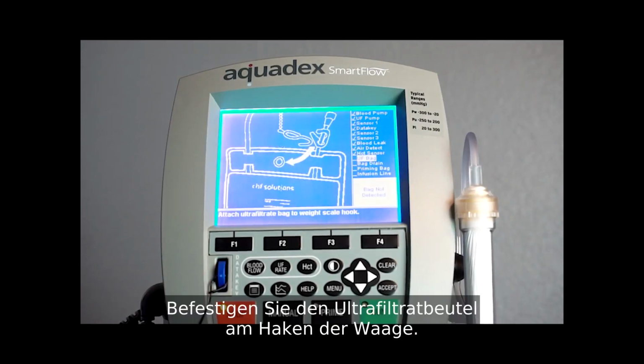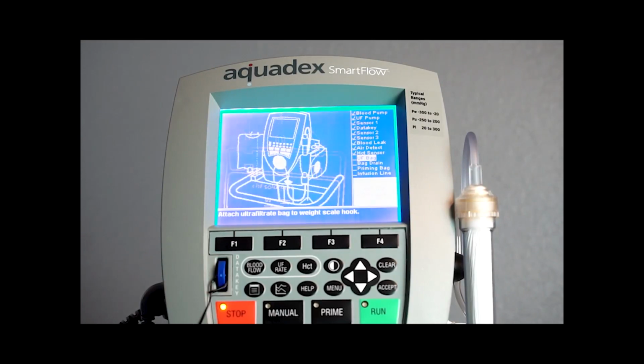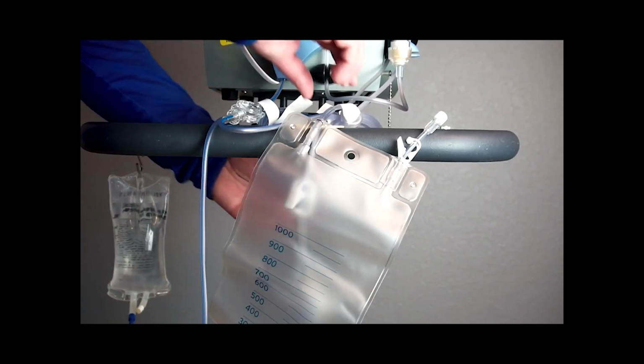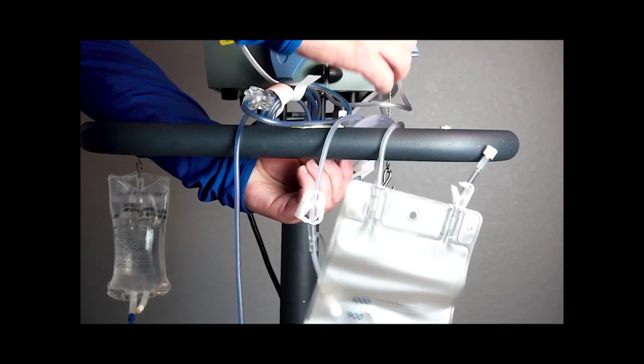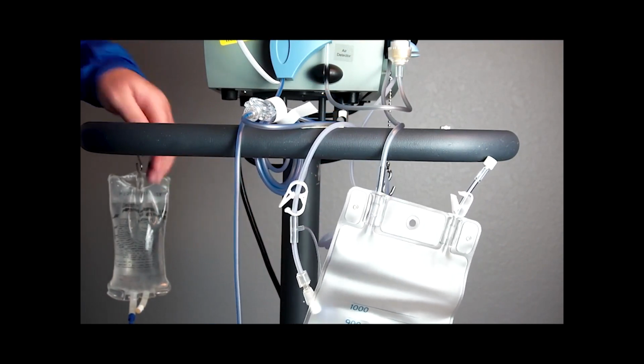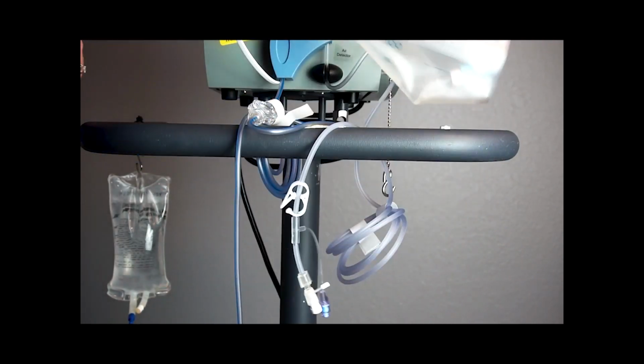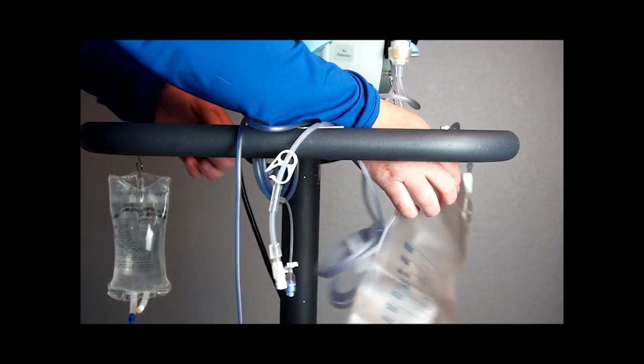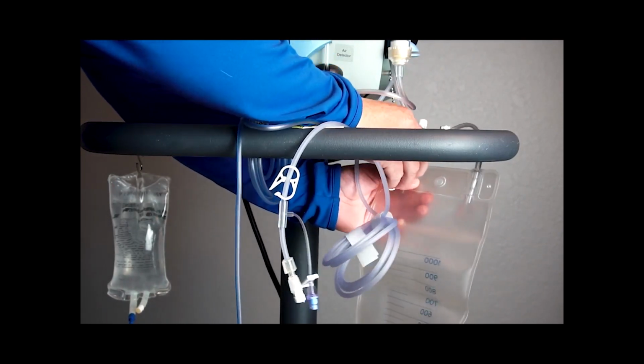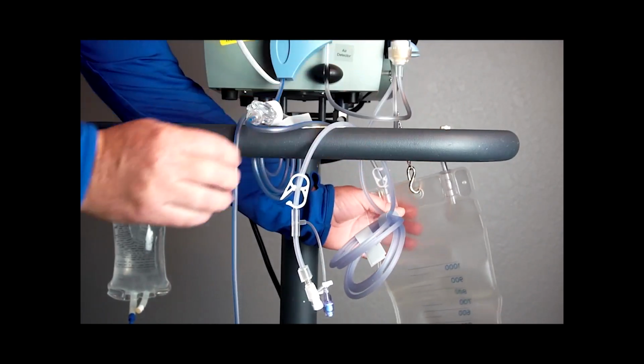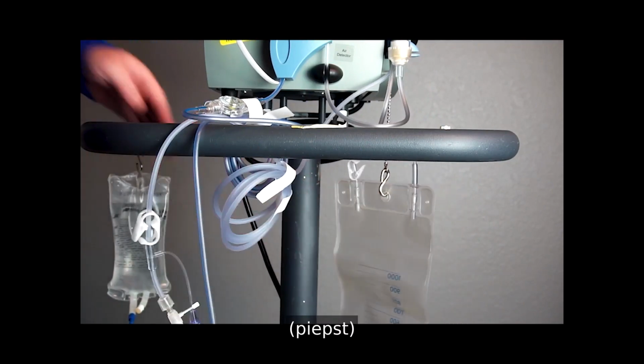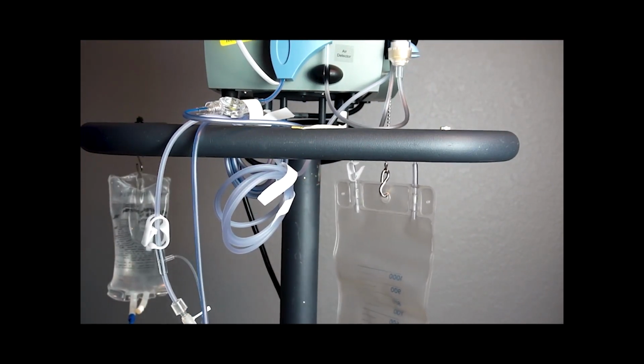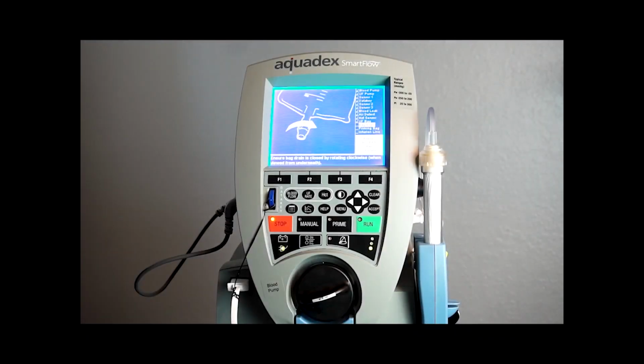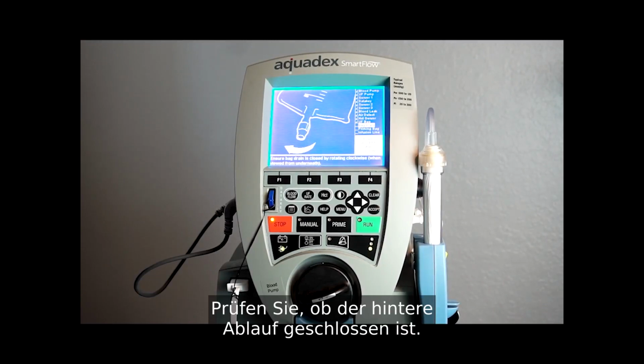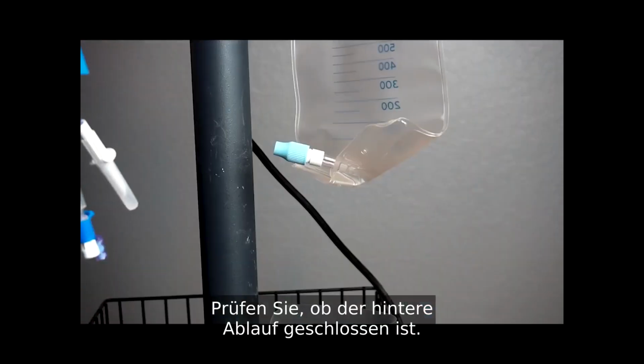Attach the ultrafiltrate bag to the weight scale hook. Ensure the bag drain is closed by rotating clockwise.